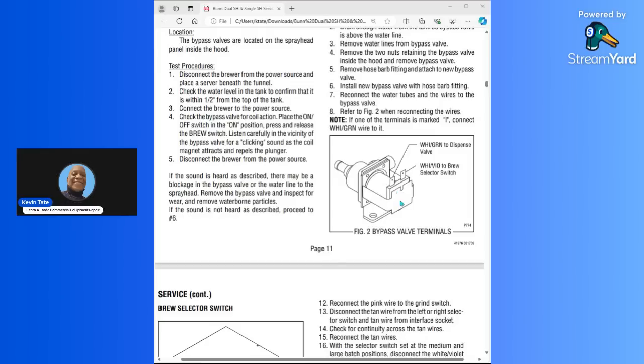So what you can do is, a lot of times you can test these coils by taking a flathead screwdriver and just placing your flathead on the tip of this metal portion right here, this metal bracket, and you will feel that the plunger is activated. You'll be able to tell because it'll pull in the flat section of your screwdriver. It'll pull in, and you'll be able to pull it off, but you'll feel the resistance there. So that's just another tip that you can use as a testing procedure along with this here.